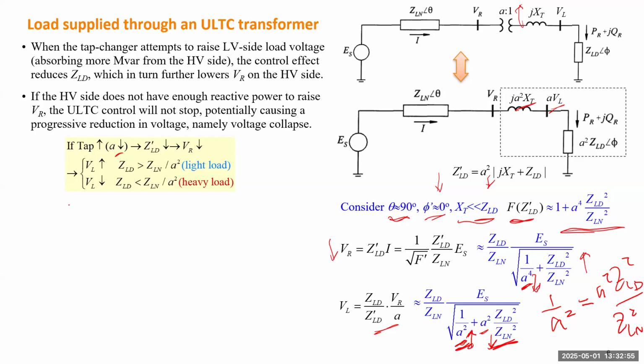But once it passes the maximum value, instead of continuing to increase the voltage, it actually decreases the voltage. So the system becomes even worse. If this transformer doesn't know, that will cause voltage collapse. So there are two possibilities. If the load is not high, when you move the tap up, the load voltage can be increased. But when the load is very heavy, the load voltage will decrease. If the transformer doesn't know, it will keep moving the tap up, the voltage will keep decreasing, and finally the system collapses.